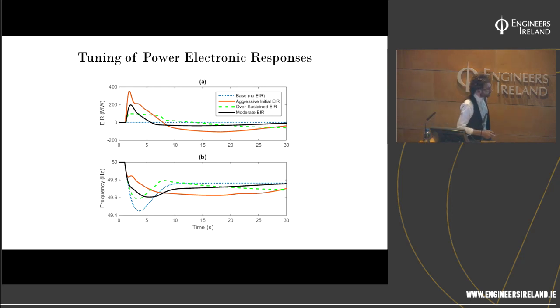So what I'm showing here is the frequency response of a system and how that changes as you change the parameters of your wind turbine controls. If you ask for a very aggressive initial response from all your wind turbines, the red one there, you're slowing down all the turbines and injecting power, but the machines have to speed back up. A wind turbine is on a max power point tracking curve. It will move so that it extracts as much energy from the wind as the wind speed changes. After an event, the inertial controls kick in, and once that injection is given, it'll hop back onto the max power point tracking curve and the machine speeds back up. That's why you have this withdrawal of energy. It happens with a synchronous machine as well, except there it's in unison with the system frequency.